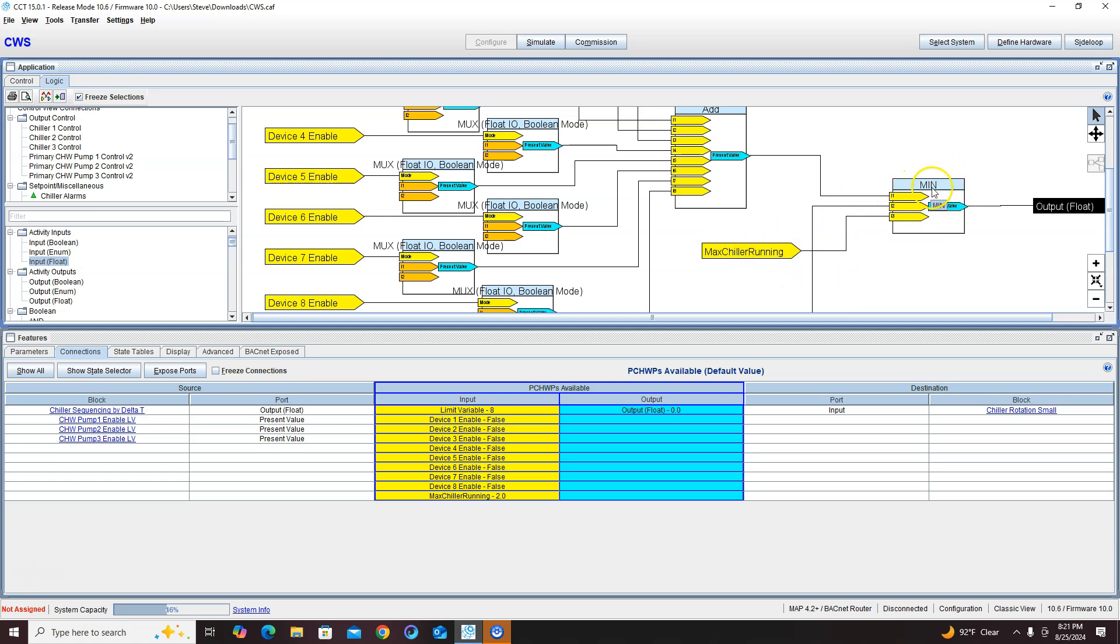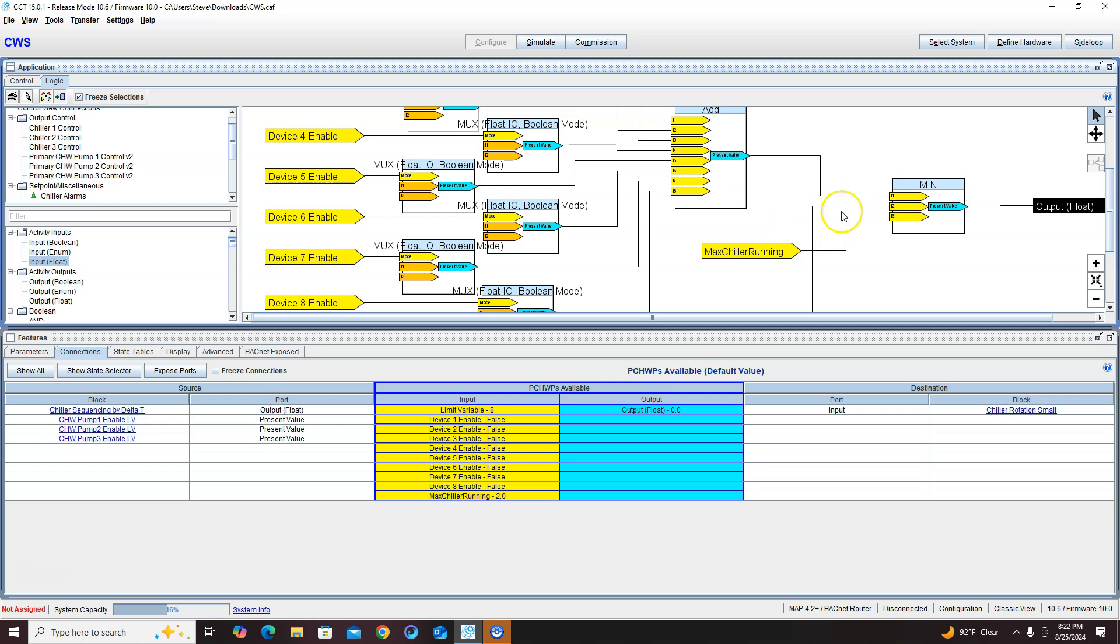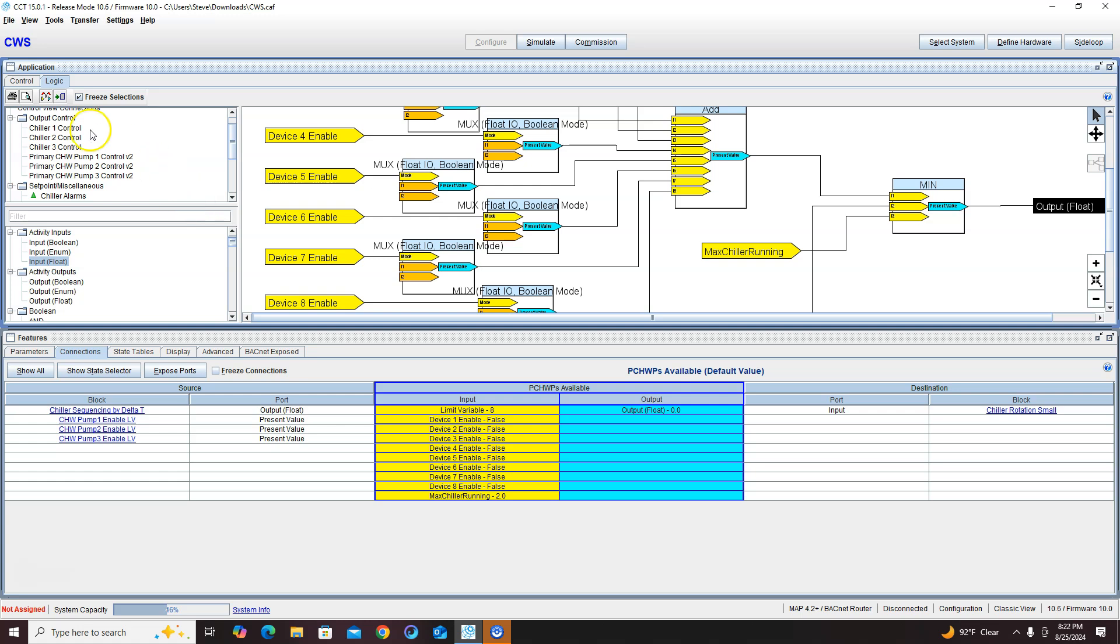Again, it'll go down to zero and it'll go up to one, two, but it'll never go past two because this is going to be the minimum not allowing it to go above two. So that's how you would do a lead lag standby on a chill water system. Thanks for watching.